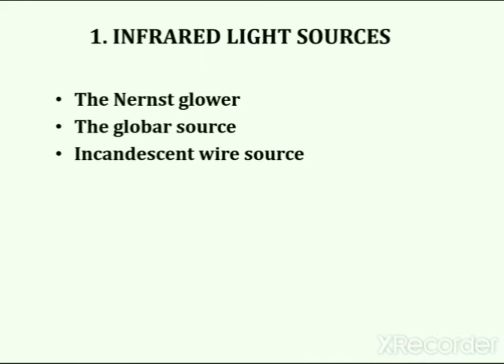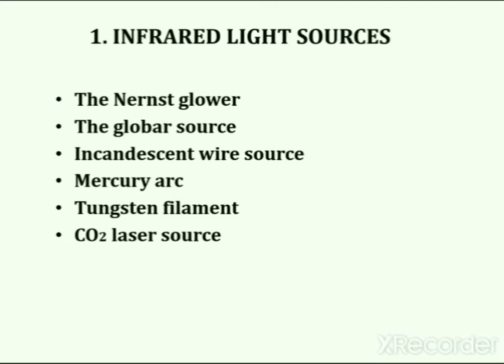Different types of light sources are used in infrared spectrophotometers. These include the Nernst Glower, the Globar source, incandescent wire source, mercury arc, tungsten filament, and CO2 laser source. Infrared sources consist of an inert solid that is electrically heated to a temperature between 1500 to 2200 Kelvin, and the heated material then emits infrared radiation.